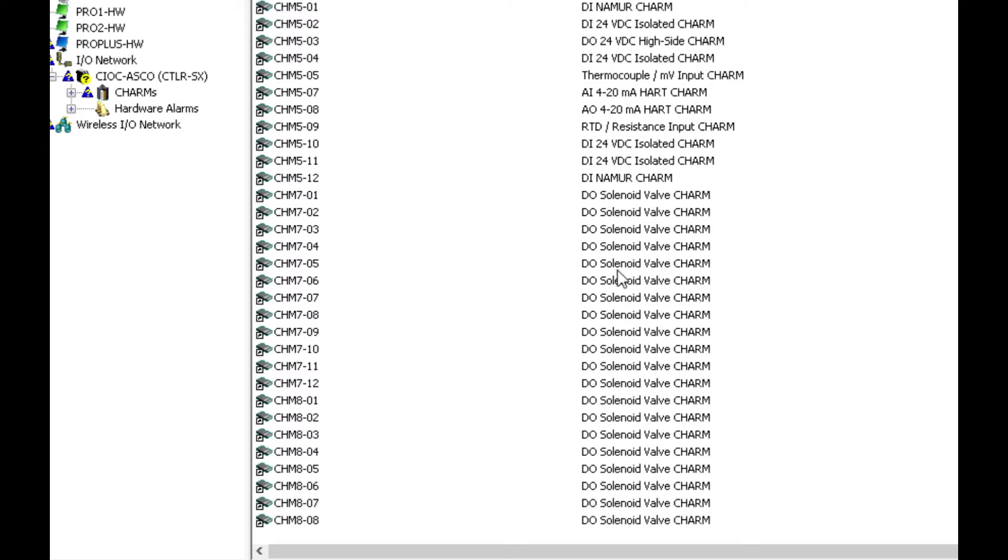So these are actually the solenoid valves that are coming in through this charm I.O. card from the ASCO 580 charm node, automatically sensed in Delta V as DO solenoid valve charm types and integrated natively into Delta V.